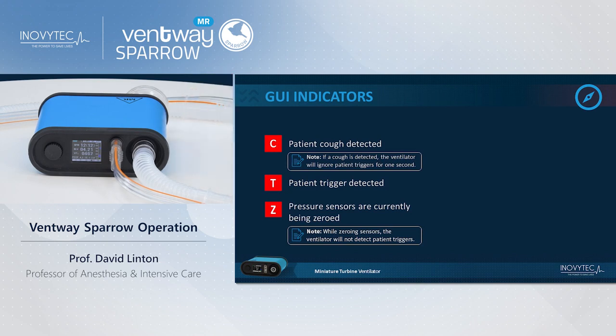If the patient triggers the ventilator and takes a few breaths, like the patient is triggering now, you will see a red indicator with a T showing you the patient triggered every breath. If you see a Z, it means that the pressure sensors are currently being zeroed, and the only relevance is that on the graphic screen you will see crossed arrows saying that it's not recording at this time.